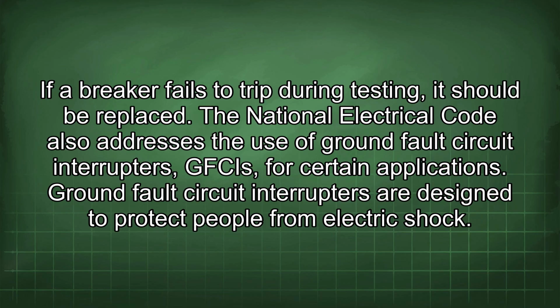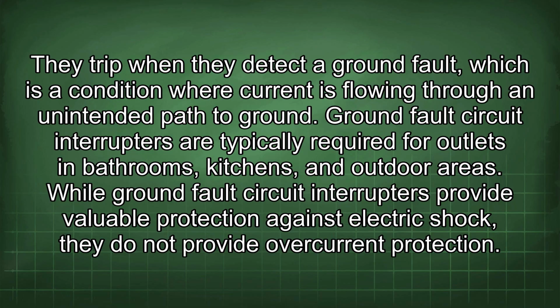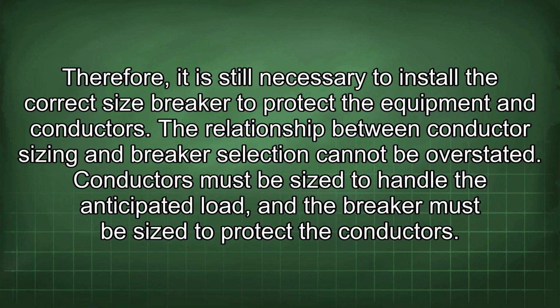The National Electrical Code also addresses the use of ground fault circuit interrupters, GFCIs, for certain applications. Ground fault circuit interrupters are designed to protect people from electric shock. They trip when they detect a ground fault, which is a condition where current is flowing through an unintended path to ground. Ground fault circuit interrupters are typically required for outlets in bathrooms, kitchens, and outdoor areas. While they provide valuable protection against electric shock, they do not provide overcurrent protection. Therefore, it is still necessary to install the correct size breaker to protect the equipment and conductors.